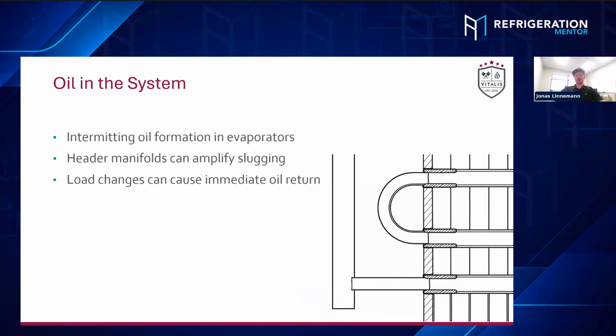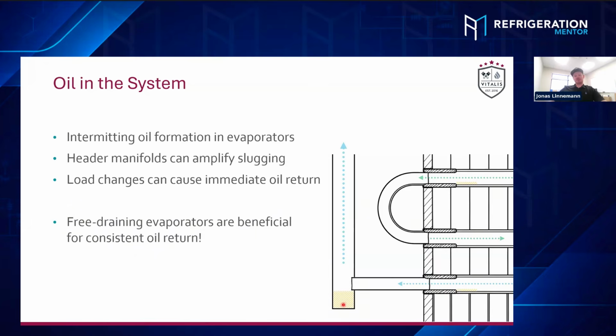So thank you. Sure. So I just talked about the evaporators. Everyone knows this air evaporator design. And as soon as the liquid CO₂ is traveling through these pipes inside, it always traps in connections to these U-bends or other conditions. It always traps a little amount of oil all along the way here. And especially if you have this header connections, you can accumulate some amount of oil, and it always tends to basically build these slugs. And then once in a while, an oil slug travels back out of these evaporators. That's where all the oil slugs basically start on the suction lines.